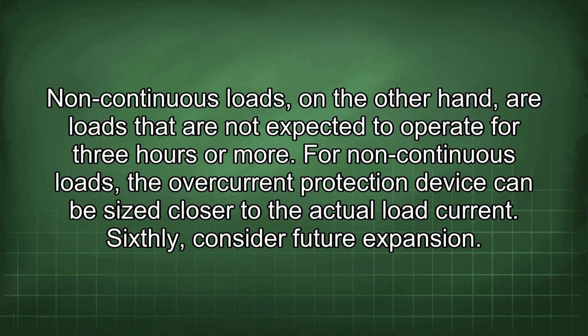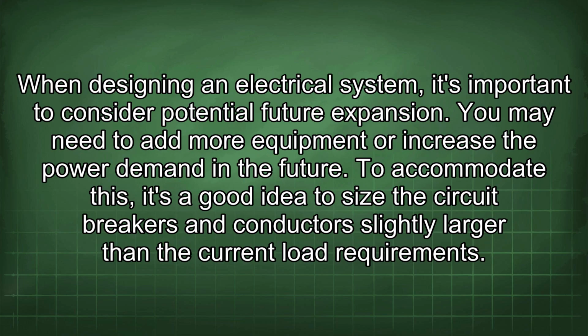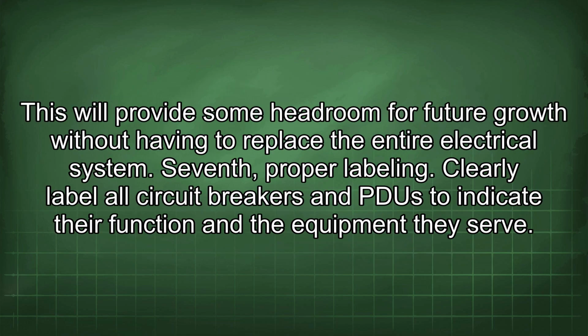Sixthly, consider future expansion. When designing an electrical system, it's important to consider potential future expansion. You may need to add more equipment or increase the power demand in the future. To accommodate this, it's a good idea to size the circuit breakers and conductors slightly larger than the current load requirement. This will provide some headroom for future growth without having to replace the entire electrical system. Seventh, proper labeling.